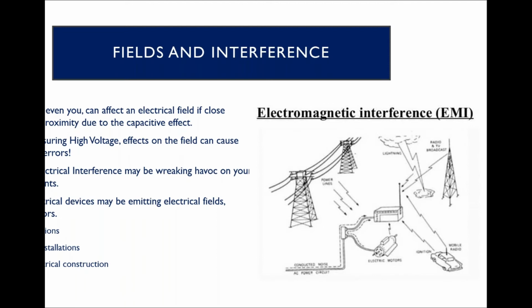In addition, there are many sources of outside electrical interference that could be completely wreaking havoc on your measurements. There's things like power lines, radio stations, military installations, even poor electrical construction in your building, which could be radiating some kind of signal that could be either affecting your source or even the electronics in your digital meters, or even the measurement points in between.